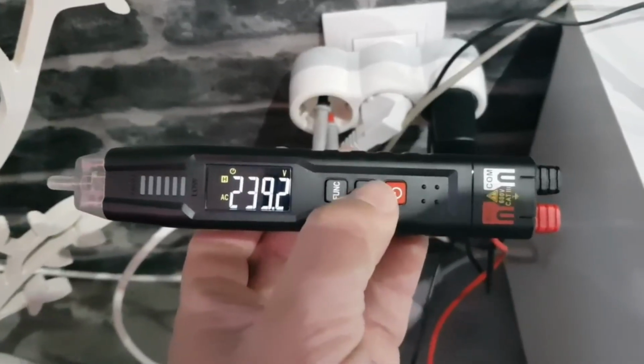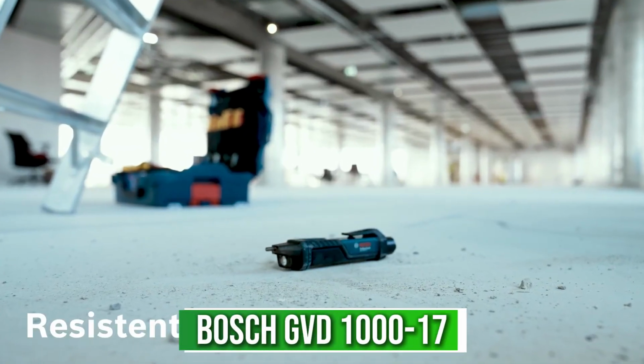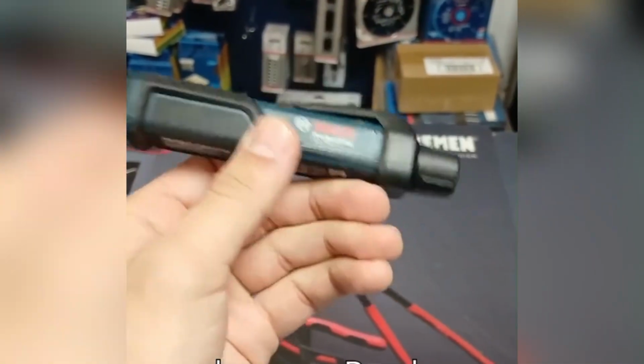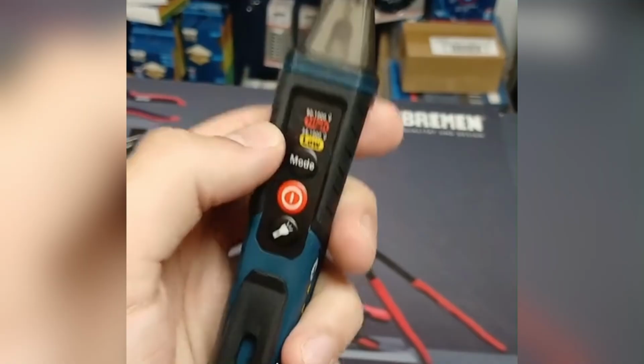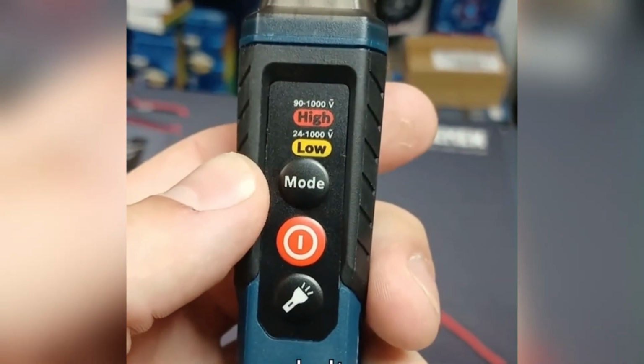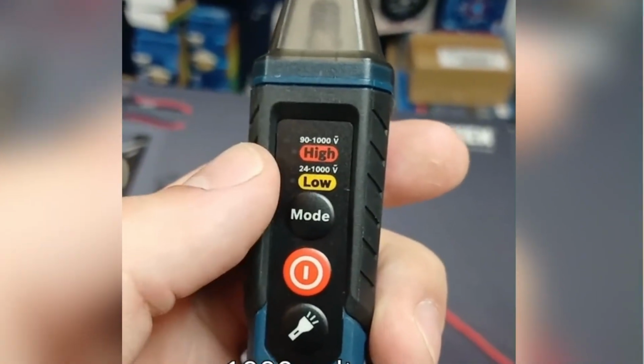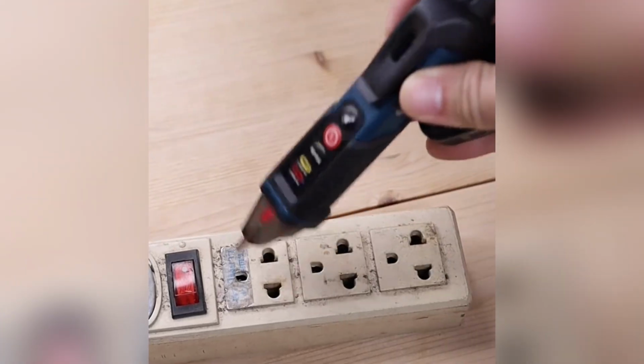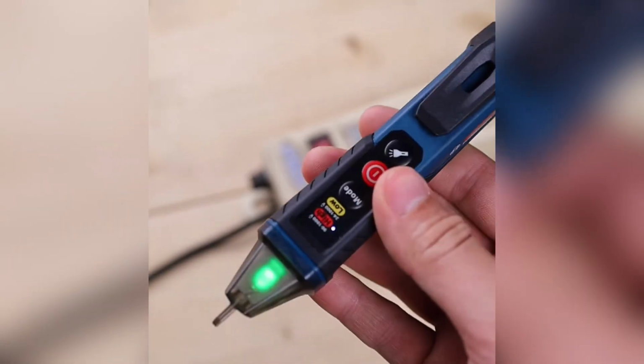The next one plays in a different league. The Bosch GVD 1000-17 is the tank of this group. 24 to 1000 volts, an IP67 rating that makes it sealed against fine site dust and fully submersible, and Cat4 at 1000 volts, the strictest classification going. It warns you 3 ways at once: sound, a traffic light color code, and a vibration motor in the grip. And that's precisely the point.